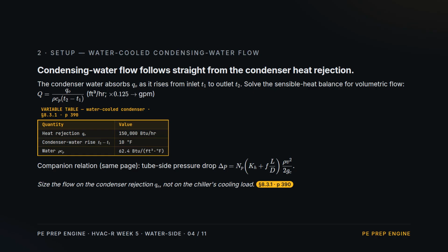Setup: the water-cooled condensing water flow. The condenser water absorbs the rejected heat as it rises from inlet to outlet temperature. So write the sensible heat balance and solve it for volumetric flow. Heat rejection over the water's volumetric heat capacity times the temperature rise. Our case rejects 150,000 BTU per hour with a 10-degree condenser water rise. 2 cautions: size on the condenser rejection, not the chiller's cooling load, and remember the formula returns cubic feet per hour. The handbook also prints a tube-side pressure drop relation alongside it.